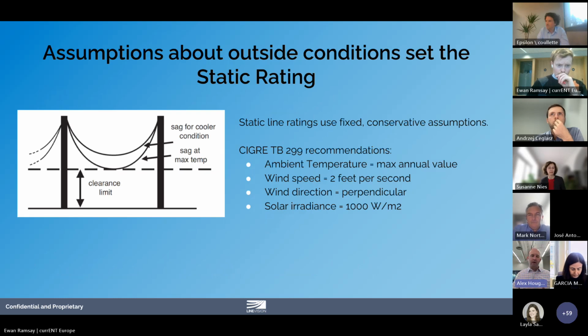So I mentioned that there are a set degree of assumptions that go into the calculation of a dynamic line rating. The most common really is the outside air temperature. So the temperature outside will have an impact on what the temperature of that conductor is. The amount of sunlight that the asset receives will also have an impact. But by far, the variable that has the greatest impact on the temperature of that conductor itself is wind. So much more so than outside air temperature, it's the presence of wind moving across a transmission line that has the potential to cool that line. And again, the cooler the line, the more power can be moved.